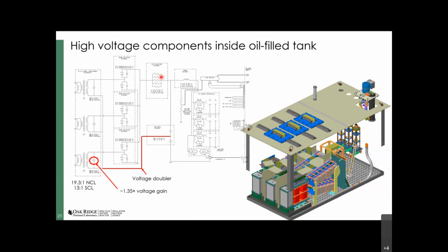There's what's called a de-Qing resistor, shown here schematically and here pictorially. That is used to damp the energy in the event of a load fault, to keep it under 20 joules, which is what the manufacturer recommends, so you don't damage that $500,000 klystron.